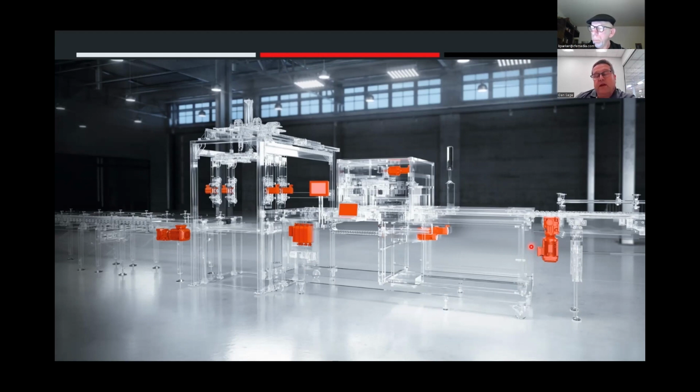So the advantage is there. If we had controls for every element out here in an enclosure, this enclosure may not fit in this area, and if this is the area we have to work with, we're in trouble. In a lot of cases, when everything is centralized, the enclosure could be 3 or 4 times the size that we have here. What we're talking about is now having other factors, larger disconnects, and heat dissipation, because all these controls are creating heat in an environment.